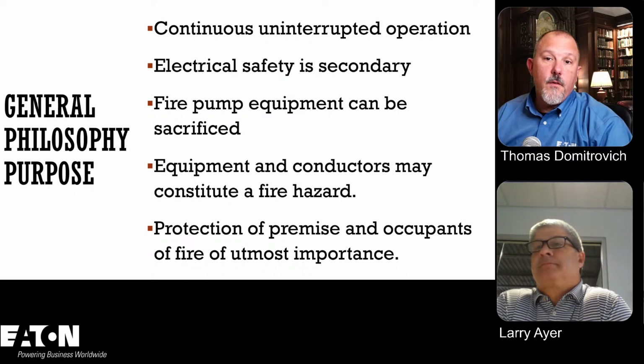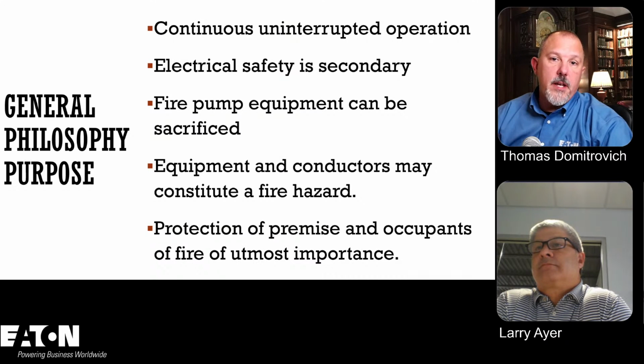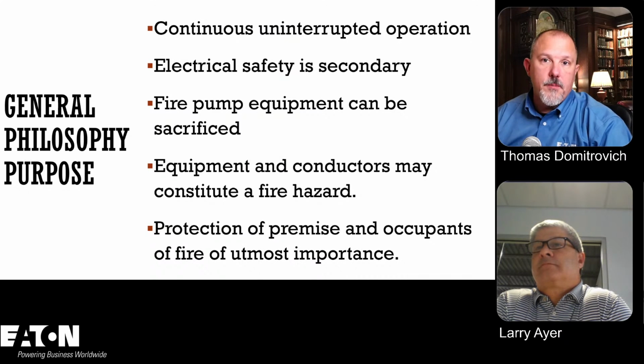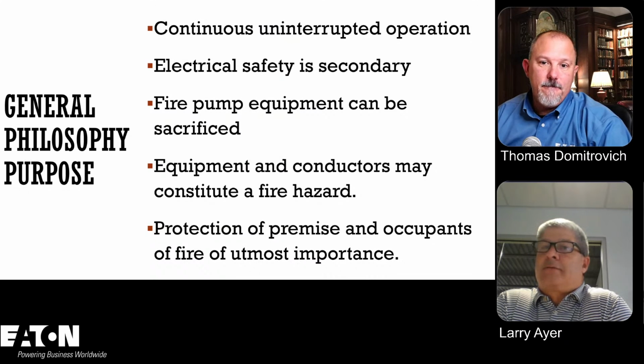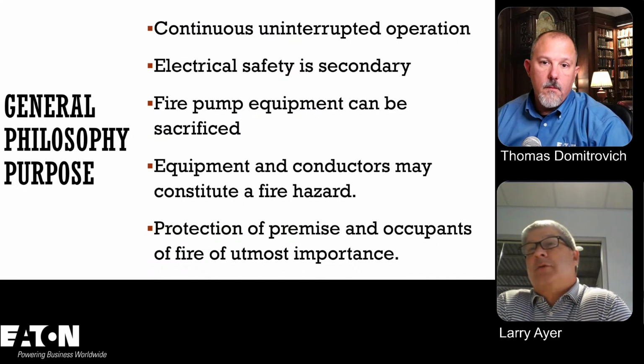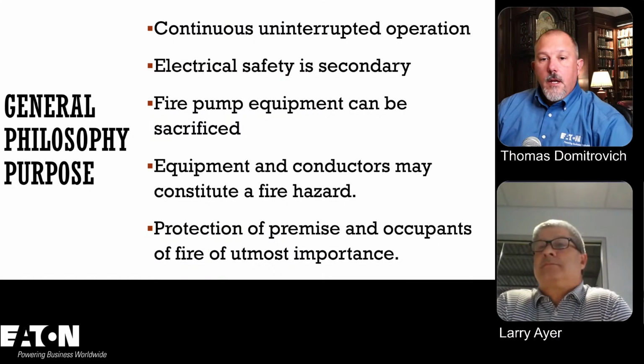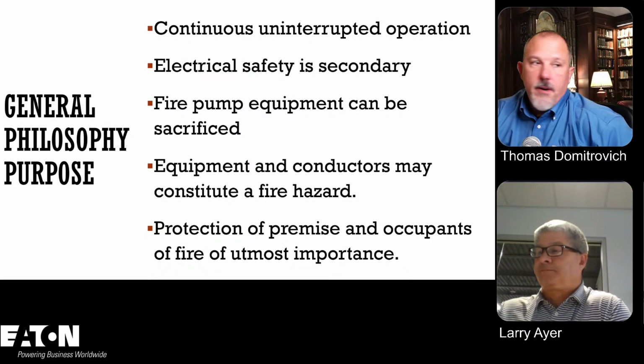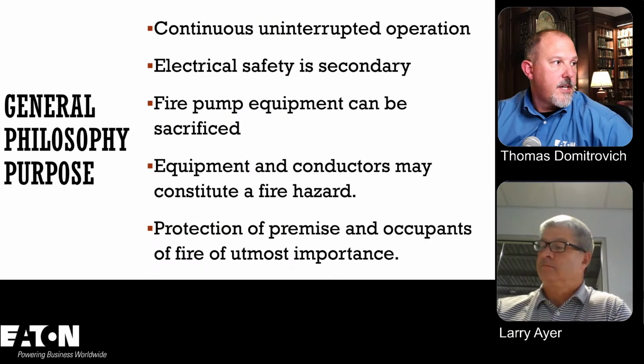Yep. So from an electrical worker perspective, there's probably a lot more precaution. Your alarms should be going off if somebody says, I need you to do some work on a fire pump system, right? Right. We need to make sure we have alarms in certain contexts and things that we find through NFPA 20 and 695. We have to make sure that we hook those alarms up so we know if someone happens to maintain that fire pump and turn it off, or if the power doesn't turn on, we want to notify people right away that something is going wrong. Yep. All right. And I think that's the primary gist of our discussion on that at that point.